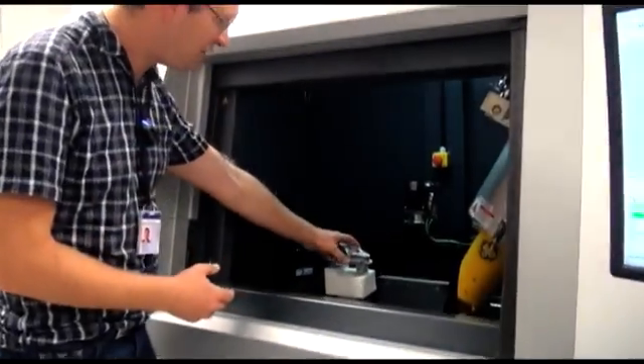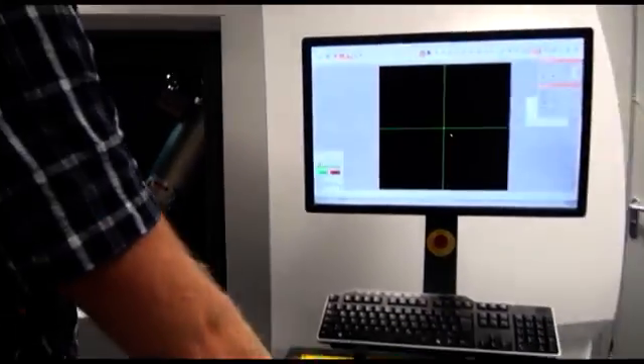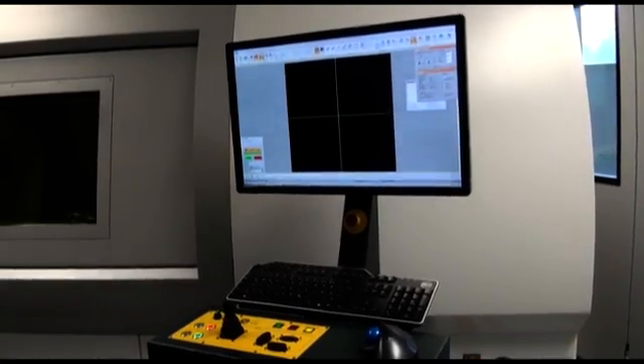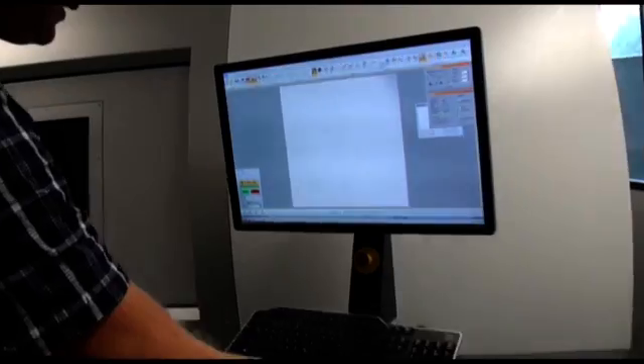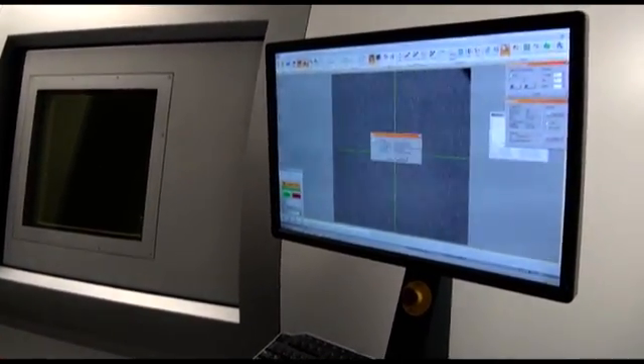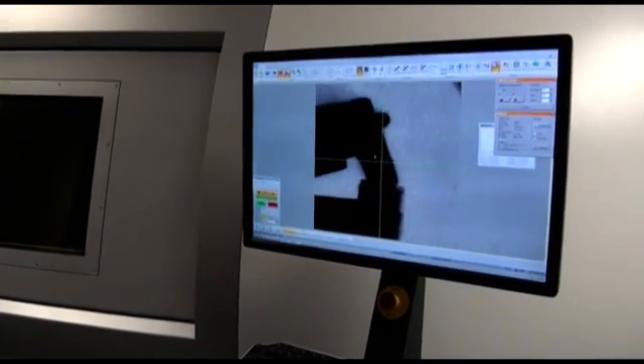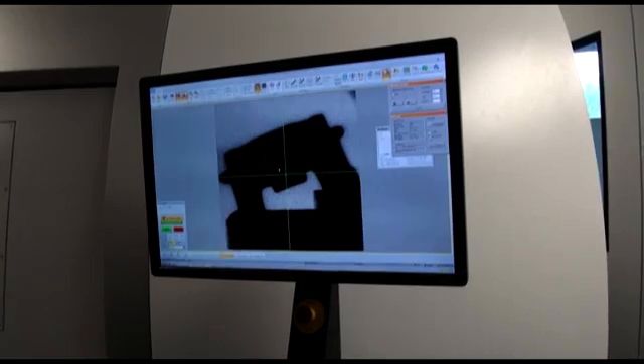This is the defined load position, so the part is now in place in a defined position. We close the door of the x-ray system. Now that the door is closed we can start the x-rays — I switch on the x-ray. When the x-ray beam is stable we will see an image from the detector with no part in the beam. Then I will move to the defined acquisition position. The sample moves to this position, which is defined so that we can do repeated scanning.